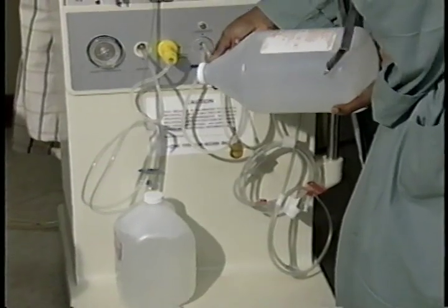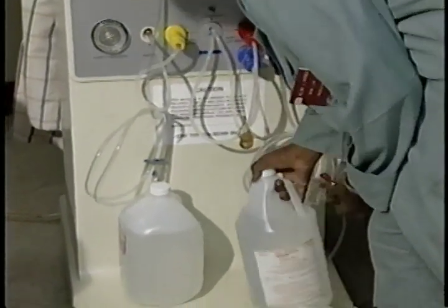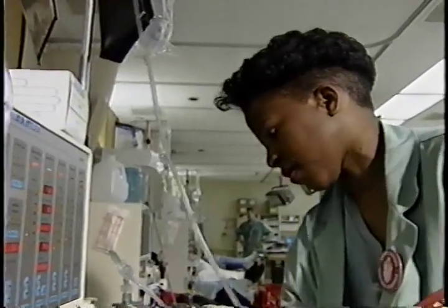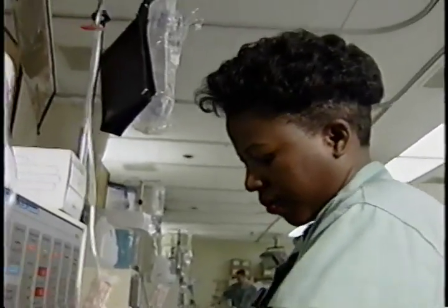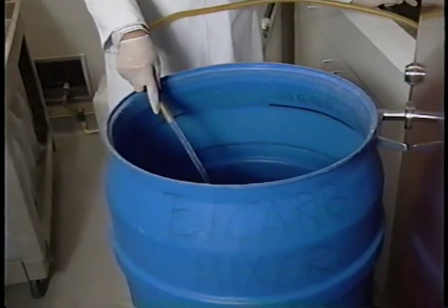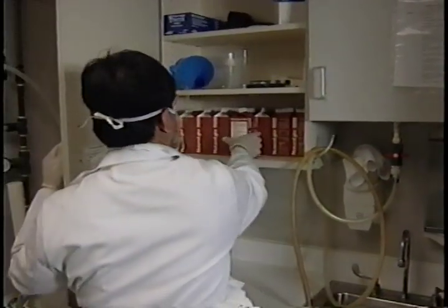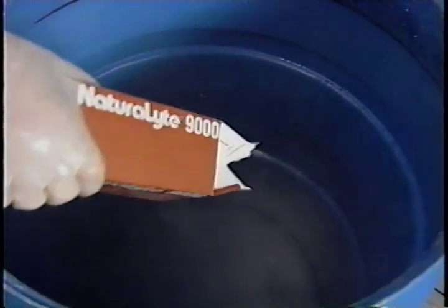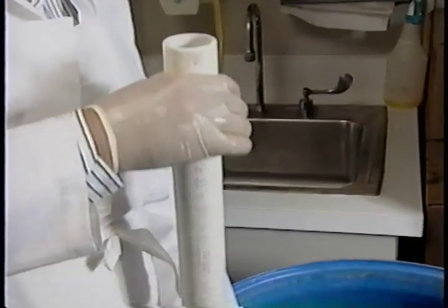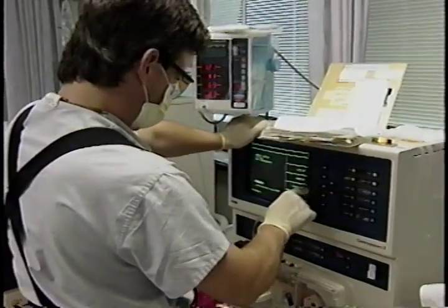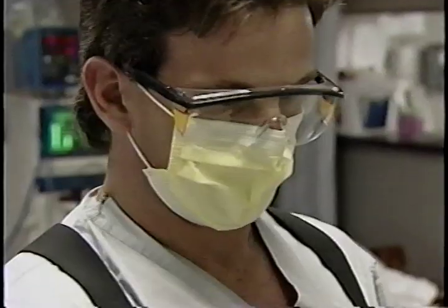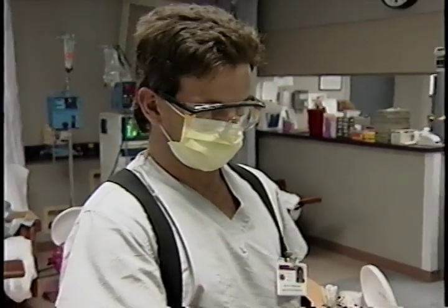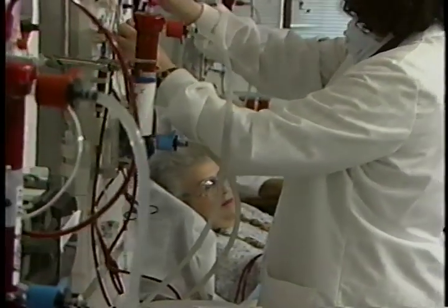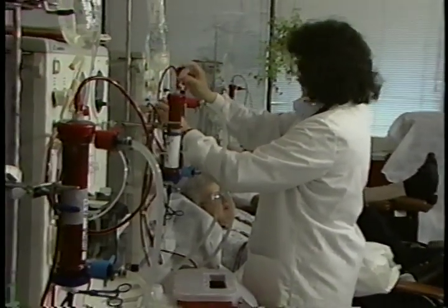Remember that the dialysate chemical composition is equivalent to a medication with the same potential for harm to the patient. The general rule is to check and double check, then check again. It is essential that your facility have adequate quality assurance procedures to make certain that the dialysate is consistent with the prescription. This is accomplished by ensuring that the proper mixing of concentrate takes place, the necessary machine safety checks are performed prior to treatment, routine or periodic preventive maintenance is completed, and that adequate patient and machine monitoring are performed during treatment.